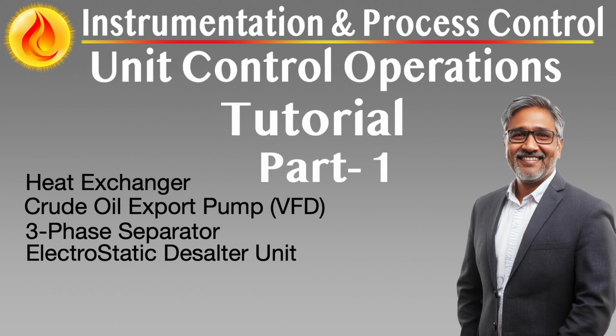Dynamic pressure control is especially critical in crude export. Excess pressure can lead to line ruptures or unsafe conditions at receiving terminals, while under pressure can cause shutdowns or non-compliance with metering accuracy. Advanced control strategies now incorporate surge detection algorithms, pressure ramping functions, and soft start sequences to protect pipeline integrity. These functions are implemented in both the VFD firmware and supervisory control logic, allowing proactive intervention in pressure excursions and avoiding the need for relief valve actuation.